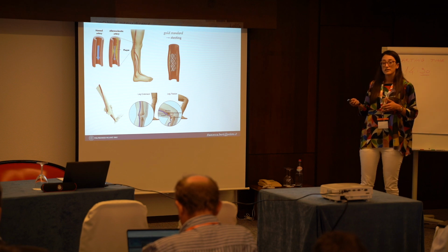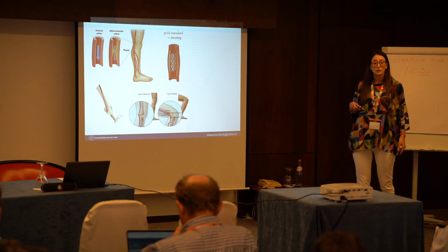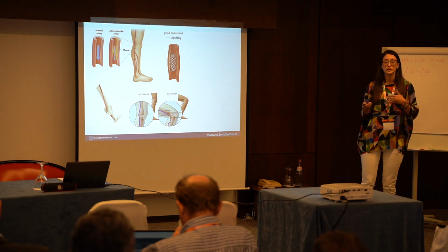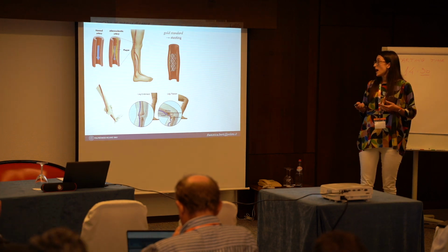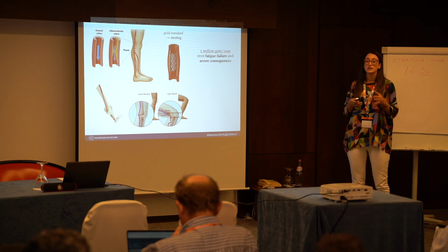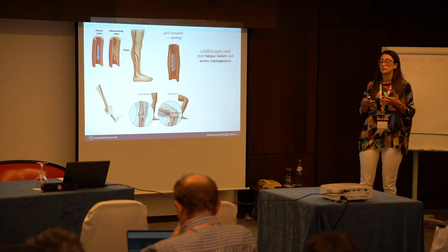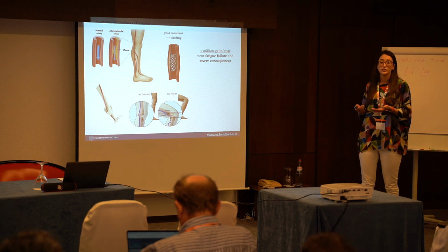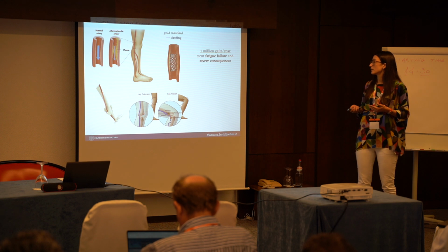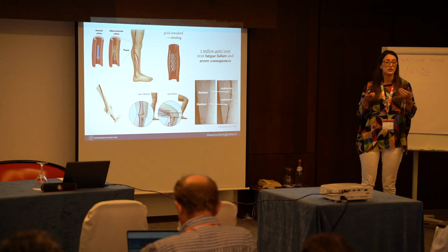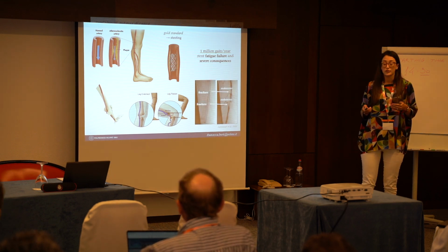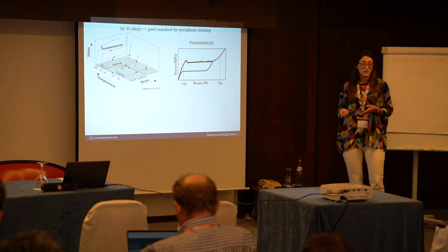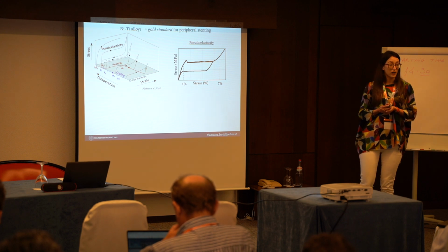However, due to gait, these arteries that pass behind our knees are subjected to a complex state of loads that are compression, pinching, bending, torsion. And if we consider that we can estimate about an average of 1 million gait cycles per year, stents are subjected to fatigue failure. And you can imagine if a stent fractures inside our body, that can have really severe consequences.